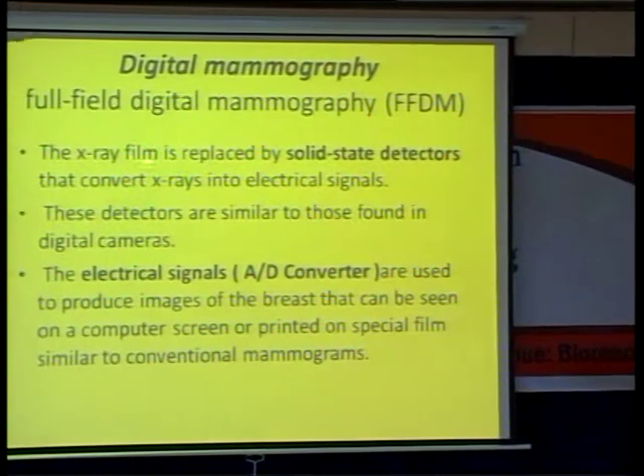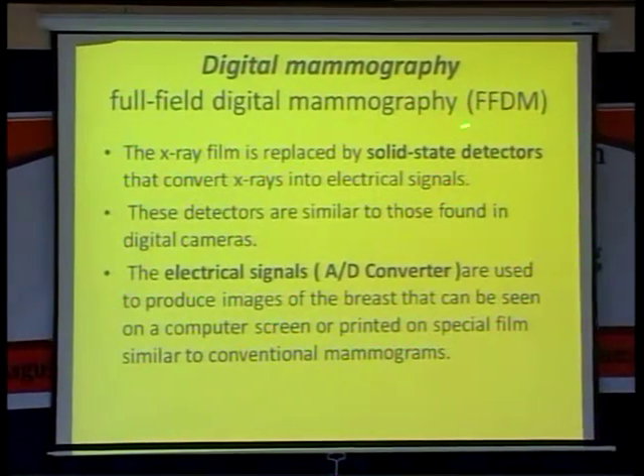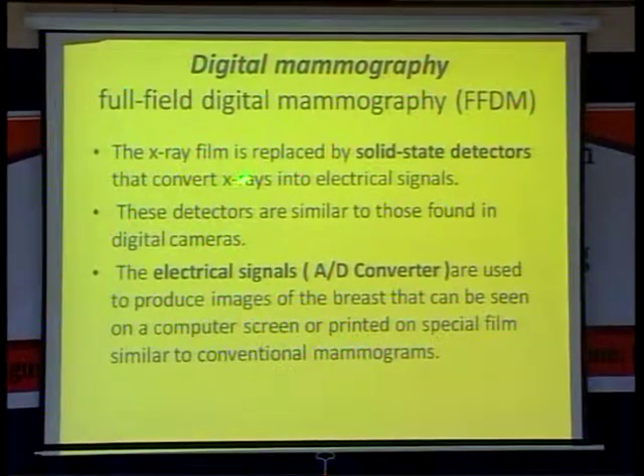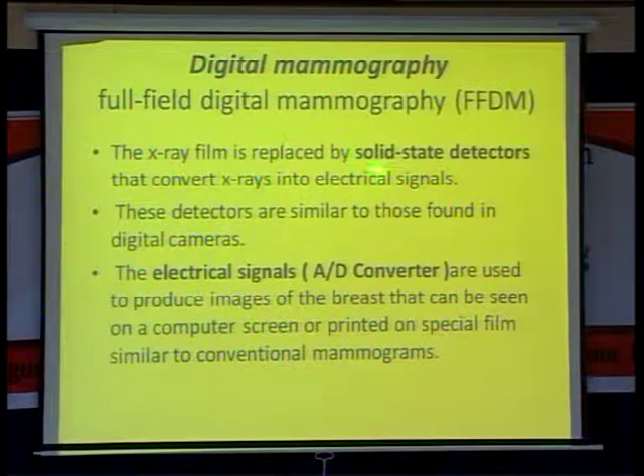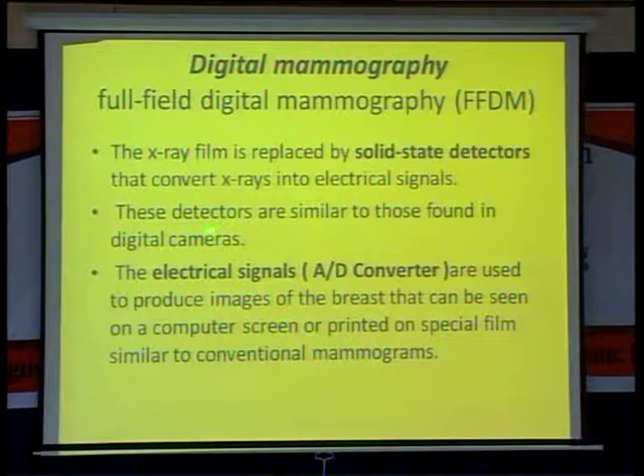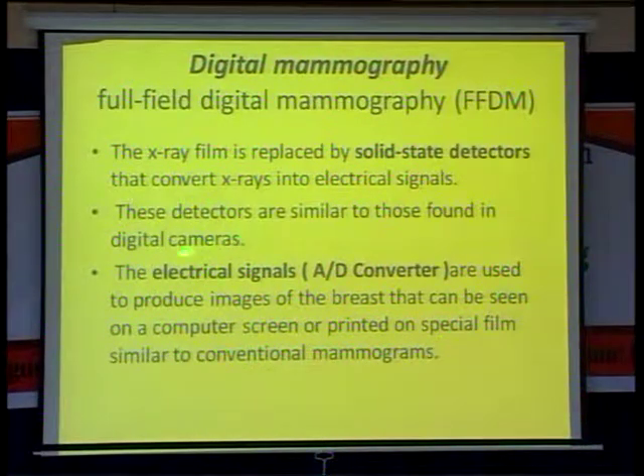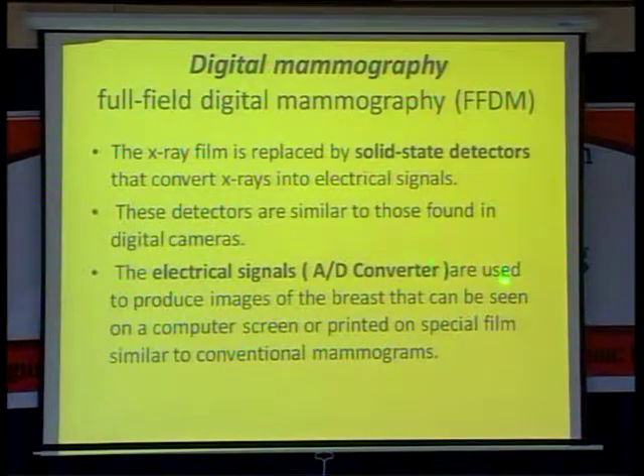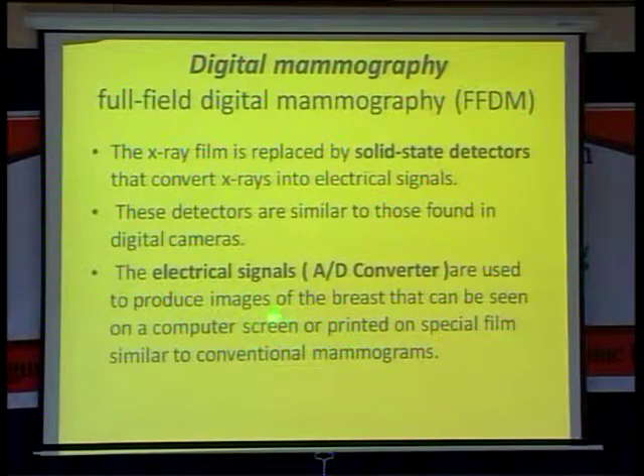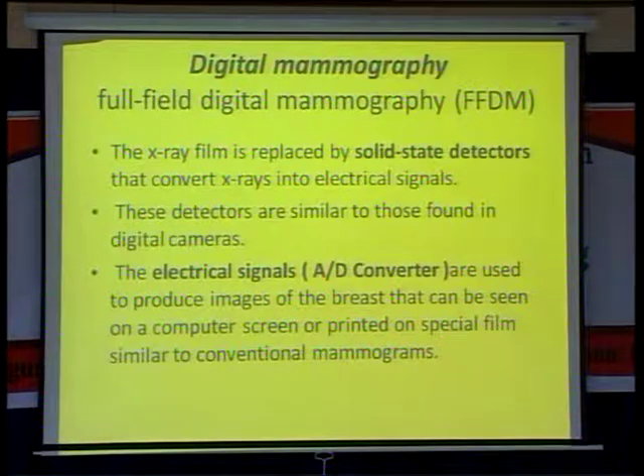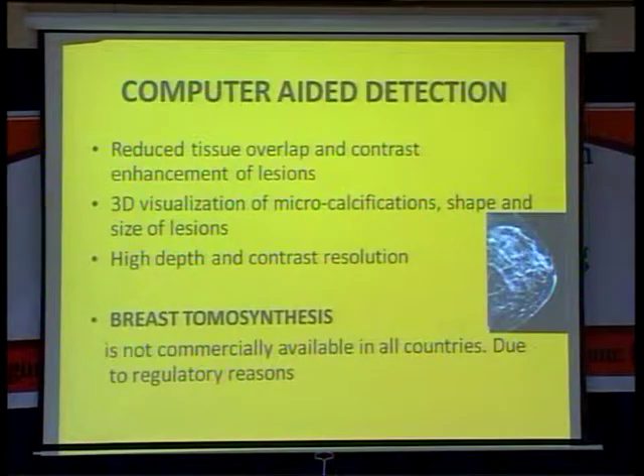In full field digital mammography, the film is replaced by a solid-state detector — a selenium detector — which converts the X-rays into electrical signals. These detectors are similar to a digital camera. The electrical signals through an analog-to-digital converter are used to produce the image of the breast, seen on a computer screen or printed on a special plate, unlike conventional mammography.